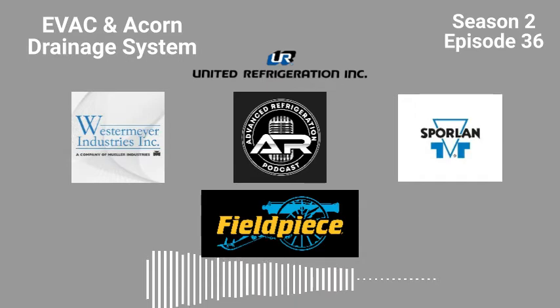And then what's actually worse is all these cases trying to fit these Acorn boxes. They're so low. These ID cases are shipping out with 1/2-inch drain ports. Coming out of the bottom of the case is 1/2-inch. Dude, a grape gets stuck in that and you're done. The grape shuts down the whole drain. But they're so low, we've actually had to take Unistrut and set the cases on strut. Wow. Because we could not get the buffer box underneath the case and drain it in there. There's physically no room between the case pan and that.